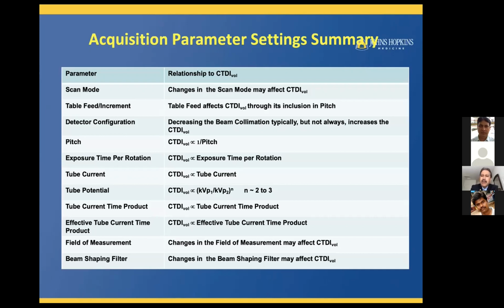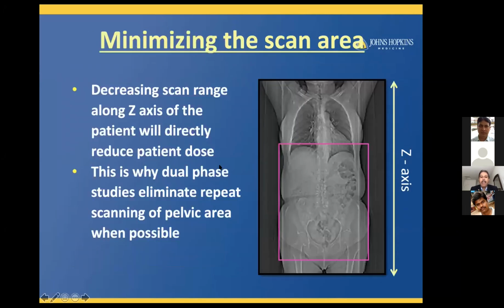These are the acquisition parameter settings summaries for the CT. The scan modes and the relationship with respect to CTDI volume is shown in this particular graph. For example, the CTDI volume is inversely proportional to pitch. For tube voltage, the CTDI volume increases proportional to kV squared, where the exponent is between 2 and 3; it's usually 2. Tube current is directly proportional to CTDI volume. So this particular parameter is showing the relationship with respect to CTDI volume in this particular case.